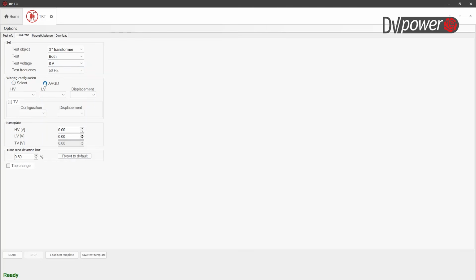We will automatically select a vector group with device, and at the end we enter the nameplate of test object, which is like that. In a first tab position, turns ratio deviation limit, this is default value 0.5%. It's defined by standards, but for some reasons you can change it if you want.